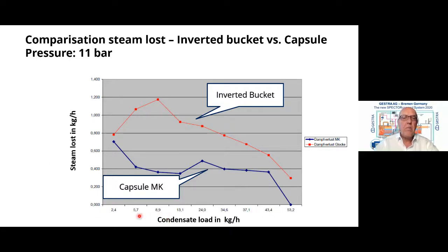But if we look at the small amount of condensate, where the steam trap has to be tight, then each steam trap works in a different way. In many applications, we run with a very small amount of condensate. For instance, in refineries, the tracing or the drainage of steam lines in every plant is only a small amount of condensate. So in many tests we have measured what happens regarding the steam loss for the different types of steam traps, and this example shows the difference in the low amount of load, that we have maybe 10 kilograms of condensate load, but the difference in the leakage is 0.4 up to 1.2 kilograms, and that makes a real difference.